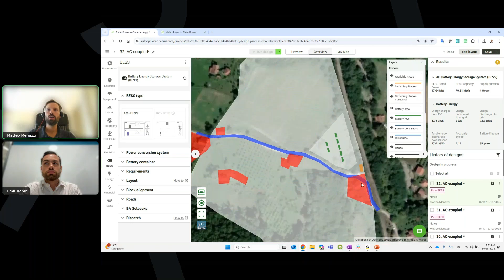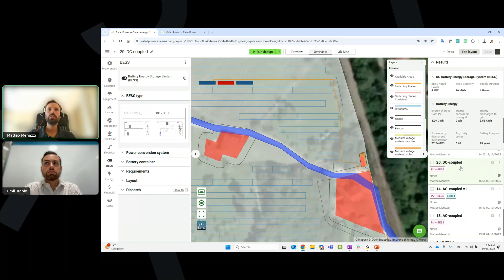What does that mean? I have here a transformer station for the PV, from low to medium voltage, and here in green, a transformer station for the storage system, connected at medium voltage level. This means I'll have dedicated inverters for my batteries and also a dedicated area. For the DC coupled setup, let me open a simulation I already have here. As you can see, the battery containers, these blue containers, are placed inside the PV field and use the same transformer station and the same inverter for both PV and BESS. So that's the main difference.